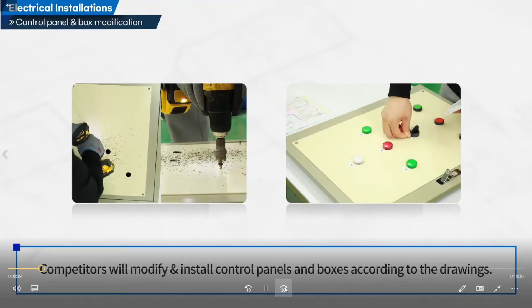Work is performed according to the drawings. Let us have a look at the key points of this task. First, look at the drawings and mark measurements on the control panel using a mechanical pencil. Draw a baseline on the control box and mark the location with the mechanical pencil according to the measurement shown on the drawings. Mark the location of holes that will be punched out on the boxes. Second, when punching out holes, make sure you hold the battery drill vertically to the control panel.